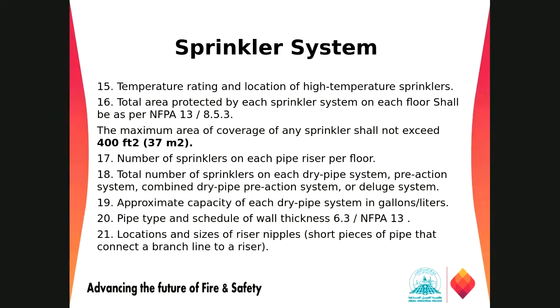And look for the number of sprinklers on each pipe riser per floor, right? So all those information we have to look into our plan, right? Not all, but as a minimum requirement while you are reviewing your plan, we have to make sure.